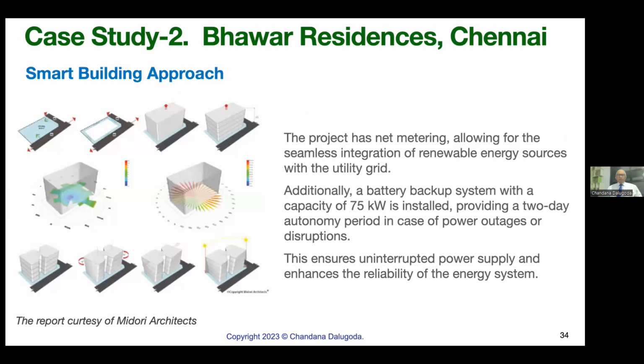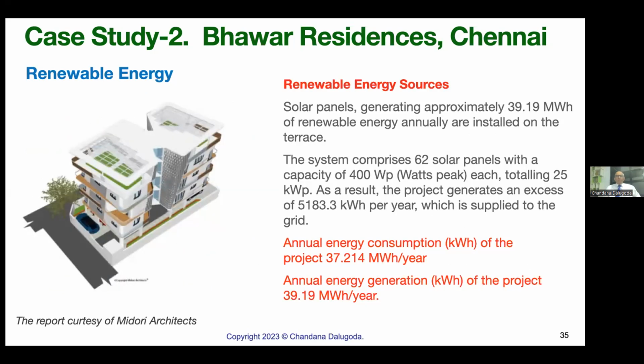Smart building approach. The project has net metering, allowing for the seamless integration of renewable energy sources with the utility grid. Additionally, a battery backup system with a capacity of 75 kilowatt is installed. Now that ensures that during the night, when there is no solar, energy is supplied to the building without using fossil fuel. So, the renewable energy sources of this building: solar panels generating approximately 39 megawatt hours of renewable energy annually are installed on the terrace. The system comprises 62 solar panels, and I will give you the final figures.